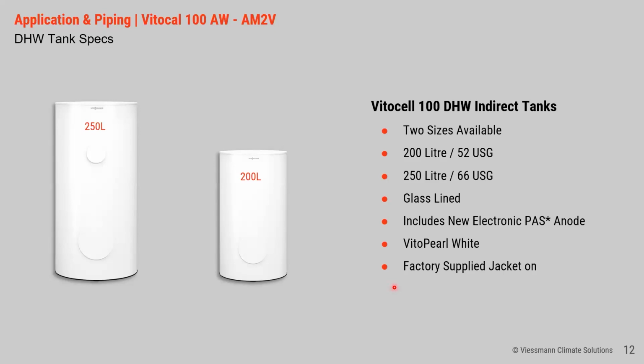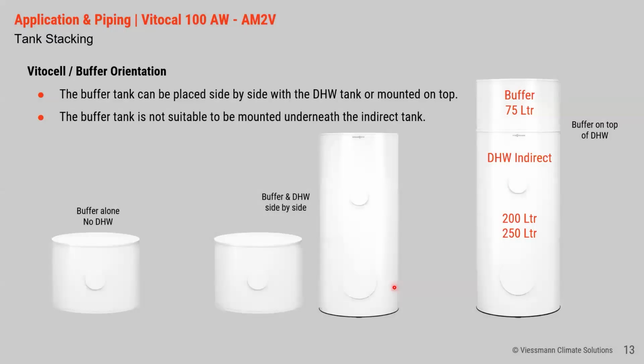Now, you may be able to use a different tank, but I'm going to talk about a few options here in a second. If you're using the indirect tanks that come with the heat pump or designed for the heat pumps, the glass line tanks, the buffer tank is designed to mount right on top of that. So if you have enough headroom in your boiler room or in your mechanical room, you can put it right on top. If you don't, you can put them side by side.